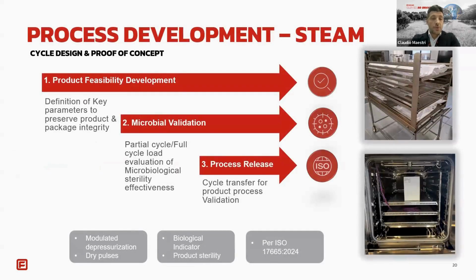How did we approach the study? First, key parameters have been defined to preserve the product and the package integrity, in particular modulated depressurization and dry pulses. Then partial cycle and full cycle load evaluation of microbiological sterility effectiveness using biological indicators, and checking the sterility of the product and the packages at the end of each cycle. Third step, the process release, meaning cycle transfer for product process validation as per ISO. The initial evaluation has been done on the nest and tub in bags without the plastic bags, as we can see here on the slide, to understand the main potential weak points of the product, and then using the plastic box containing the nest and tub, as we can see here on the right.